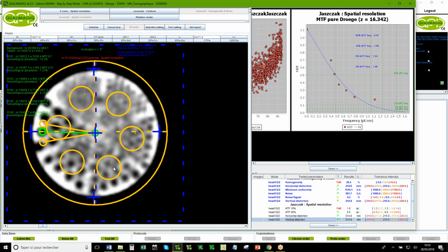Normally here it's a visual method. Finally you declare I can see maybe this target, but after, not really. But you can quantify with the Droege and Morin method. So the rest is to evaluate also the spatial resolution with some line sources.